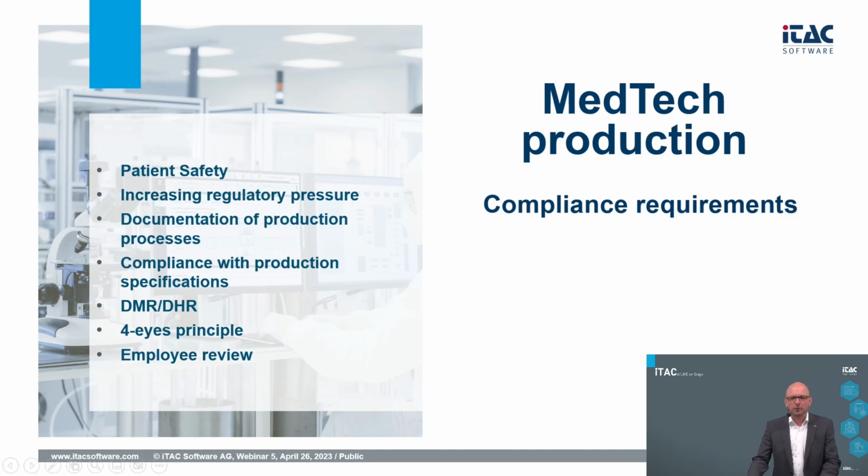For sure, we are talking about the device master record, which is the base, which describes how it should be, and later on about the device history record, which describes how a product has been realized. For sure, other things like the four-eyes principle are important, and also the employee review.